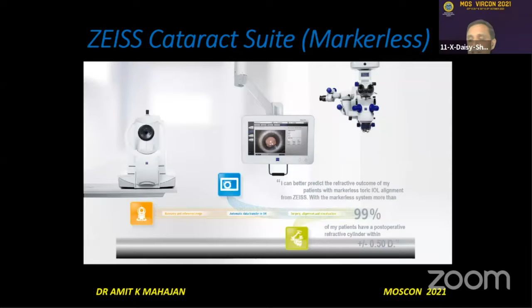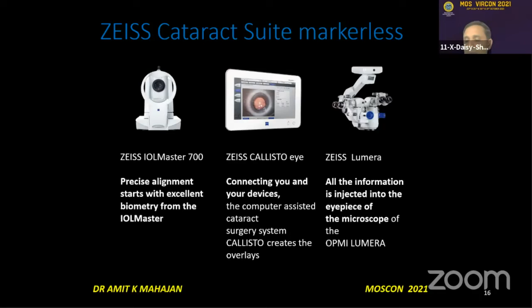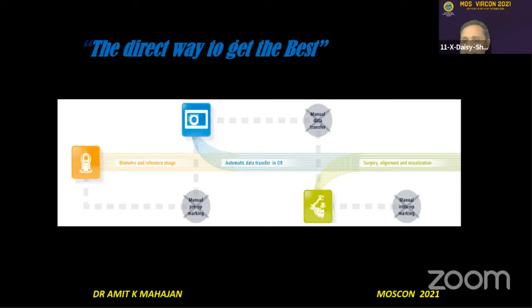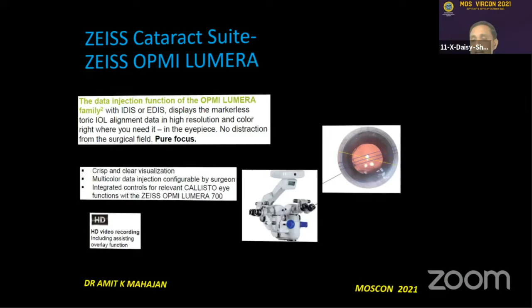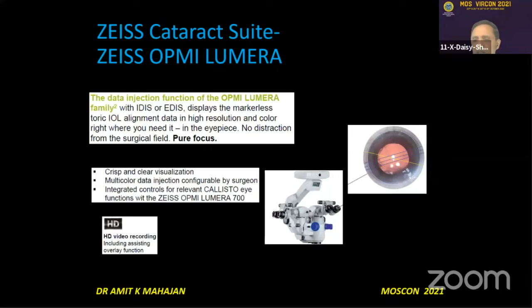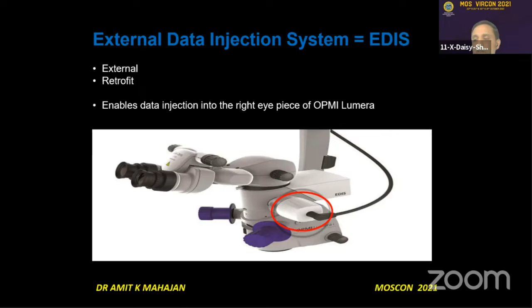Now, in order to overcome all these issues, Zeiss has introduced the markerless suite for the toric IOL. It consists of IOL Master, Callisto Eye, which picks all the data from the IOL Master and projects it to the Lumera microscope. All these three instruments work in a directly coordinated fashion, and Callisto matches the reference image for the alignment of the patient's eye and continuously tracks the image to provide a display overlay over the right eyepiece of the microscope. It gives very crisp and clear visualization in high resolution and multicolor overlay in the right eyepiece. And it is not bulky. It is only this small external retrofit IDIS, or what you can call a data injection system. And this is all that is required for giving you the excellent overlay.